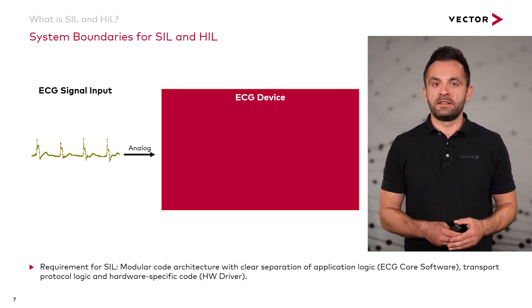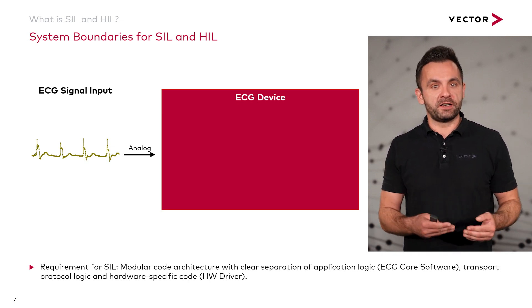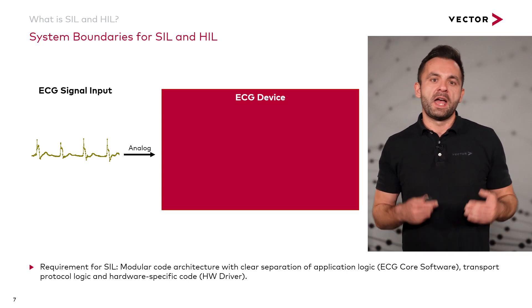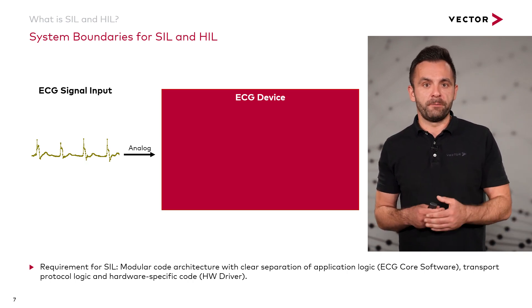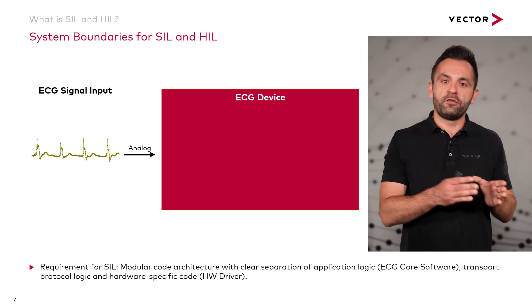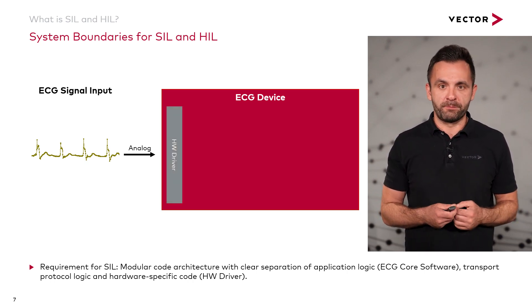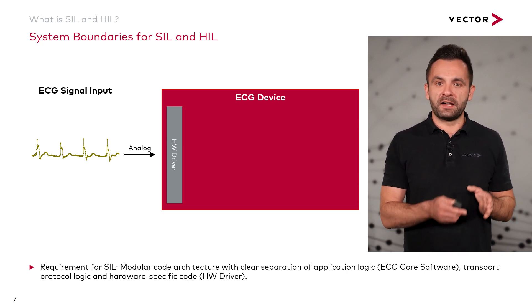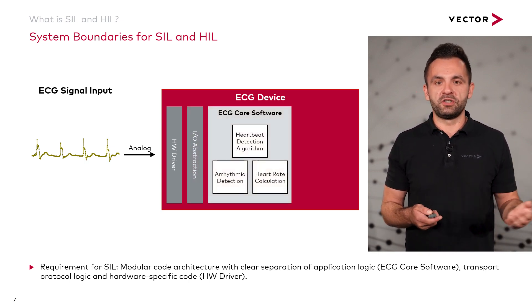Let's take a closer look at the internal software architecture to understand which software components are tested with SIL and which with HIL. The analog ECG sensor data is processed by an analog-to-digital converter which writes integer values to a register to represent the time series of the measured input. This register is read out by hardware and platform dependent software — here called the hardware driver. This hardware driver passes the time series through an I/O abstraction layer to the main part of the device's software: the ECG core software.